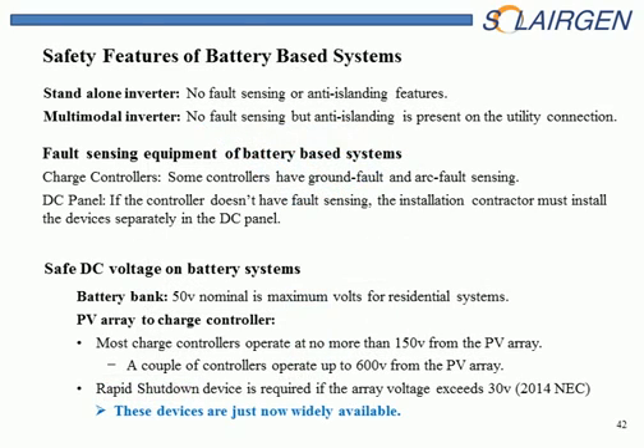So let's look at these safety features that are built into these battery-based systems. Standalone inverter, there's no fault sensing or anti-islanding feature. Of course there isn't an anti-islanding feature because it's not connected to the grid, but the fault sensing is actually in the equipment such as the charge controller or in a DC panel, so the inverter doesn't do this. With a multimodal inverter, if it's in sell mode, then it would have the anti-islanding feature, of course, so that would shut down. So the charge controller or the DC panel is where your fault sensing, your ground fault, and your arc fault would be. So they'll do the job that the interactive inverter was doing with the interactive systems.